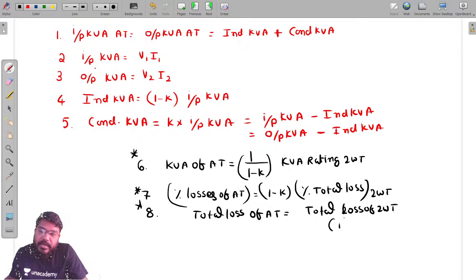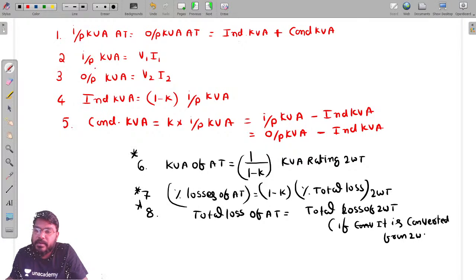So if conversion takes place, if it is converted from the two winding transformer - when we convert a two winding transformer's losses into an auto transformer, the percentage losses change, but the total losses in kilowatts or watts remain the same.